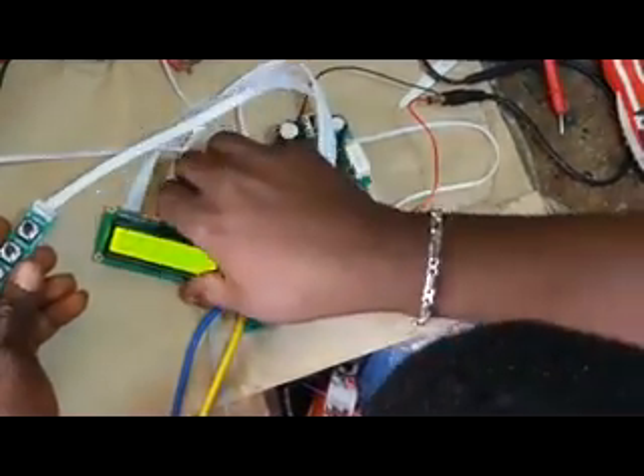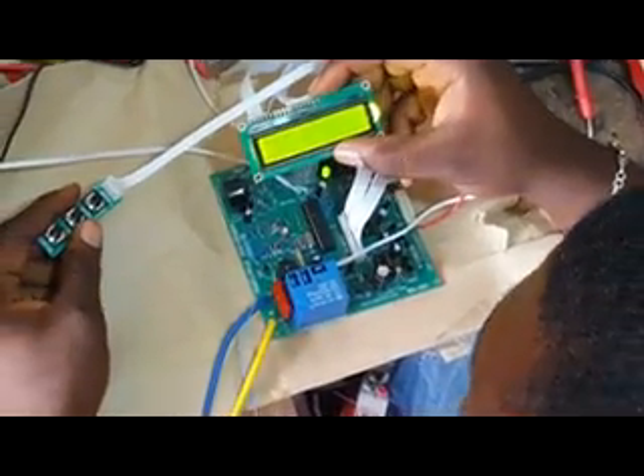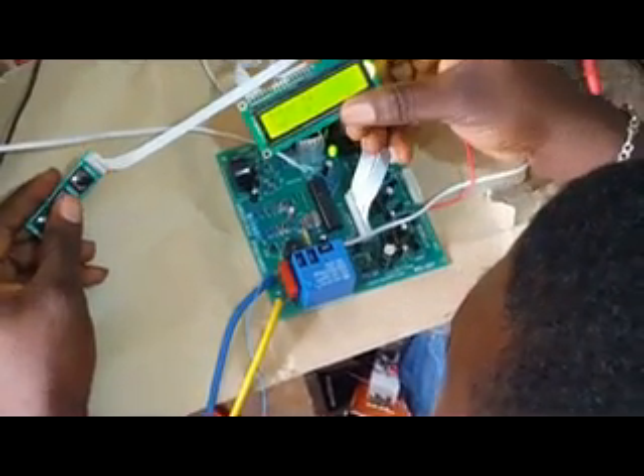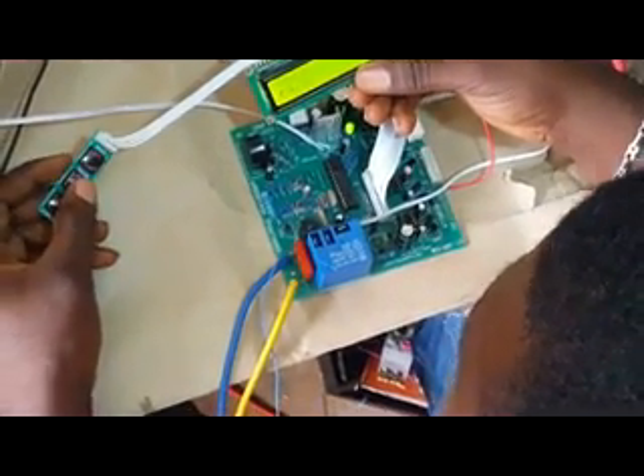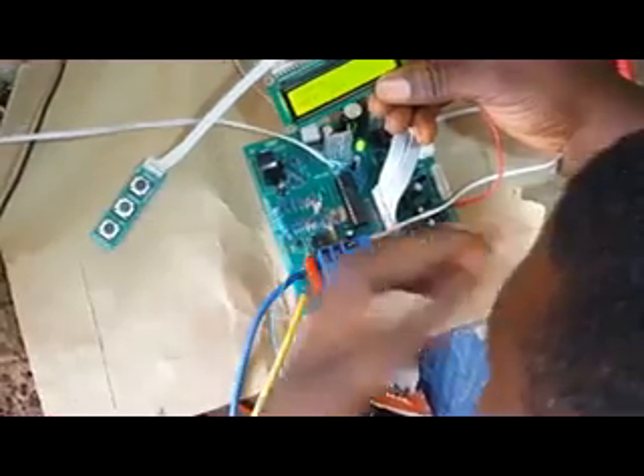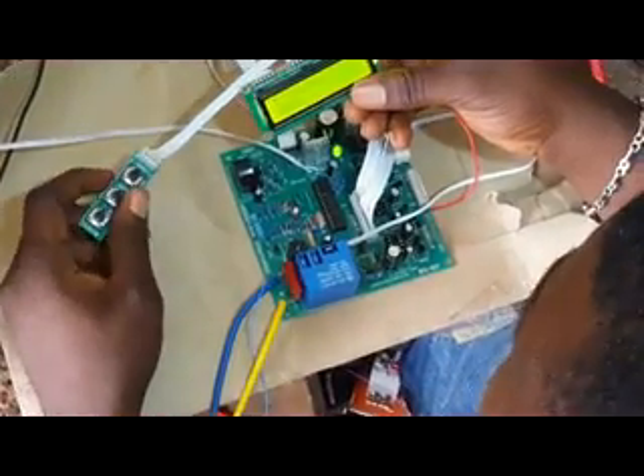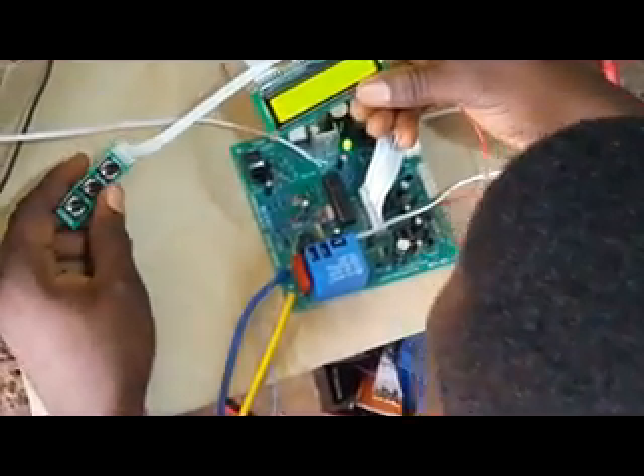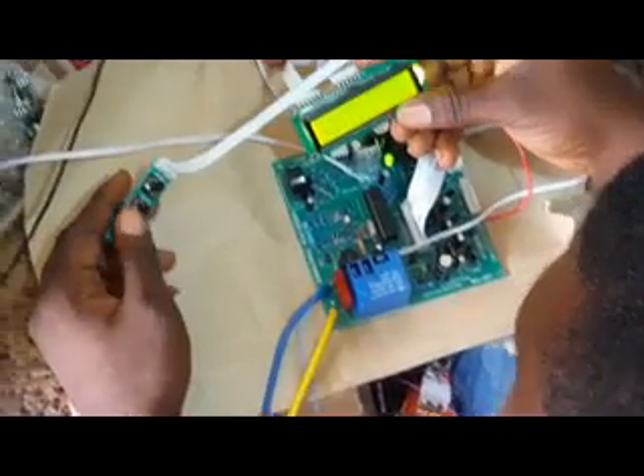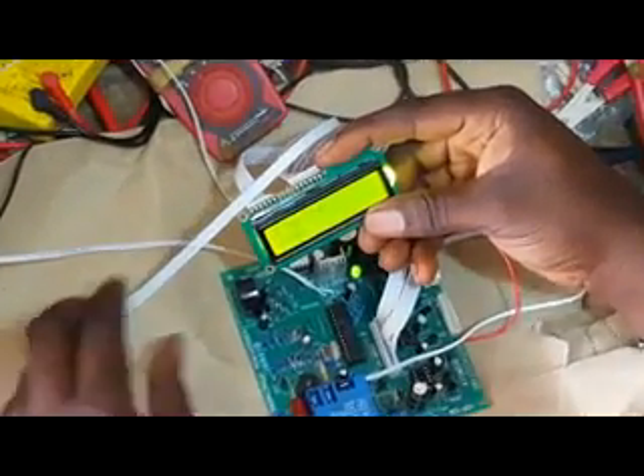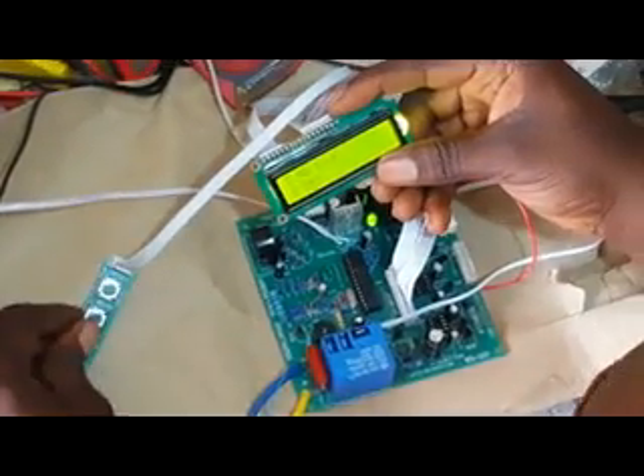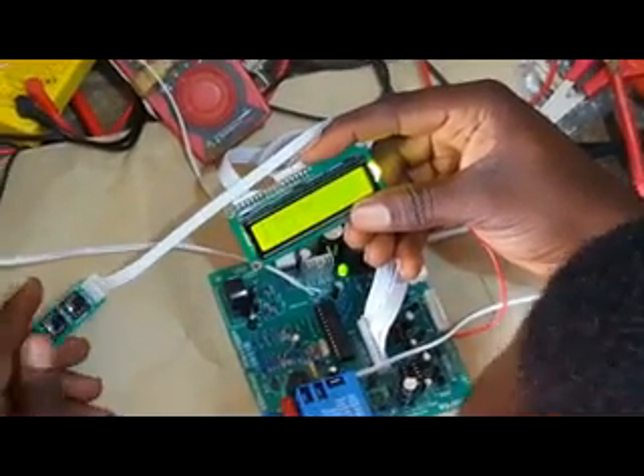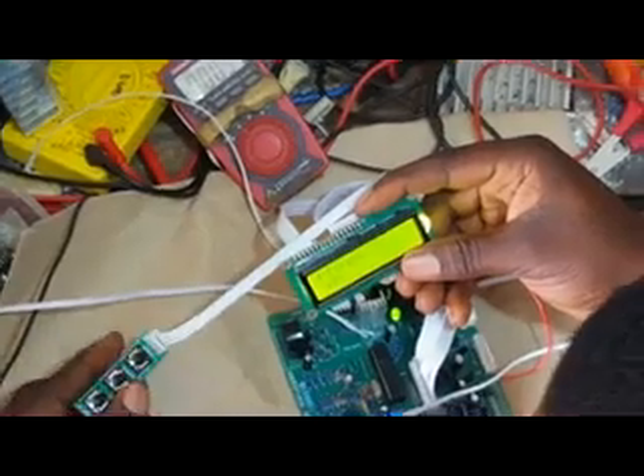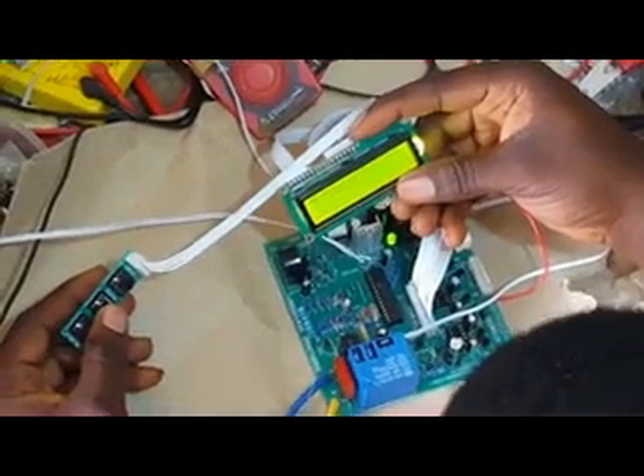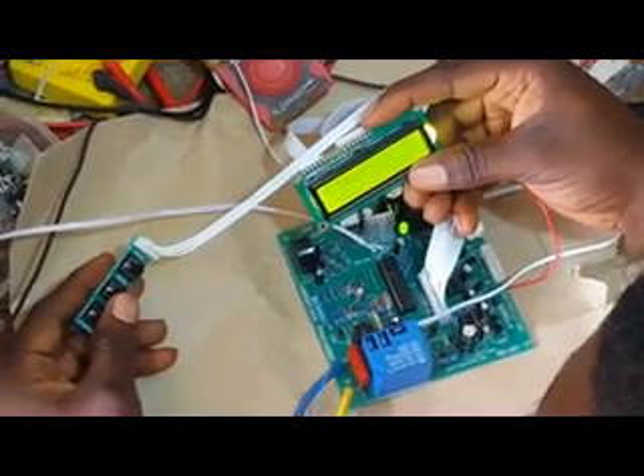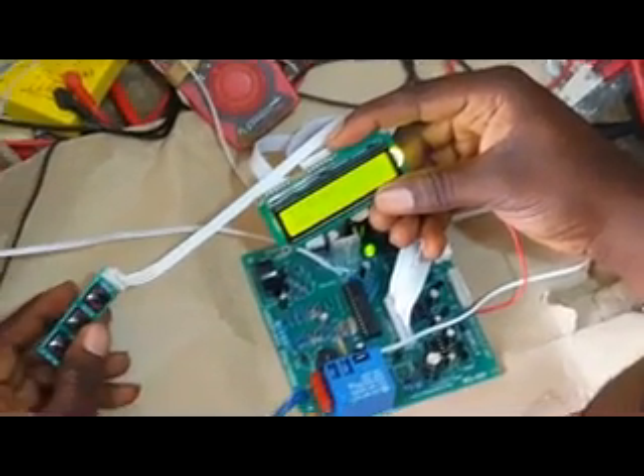Now it's asking me enter setup. N means no, Y means yes. So press enter. Version 4.3, and this is calibration. Number 1 is calibration, number 2 is no load test, number 3 is option, number 4 is parameter, number 5 is discard, and 6 is done. That's if you're throwing it out, or you're calibrating.